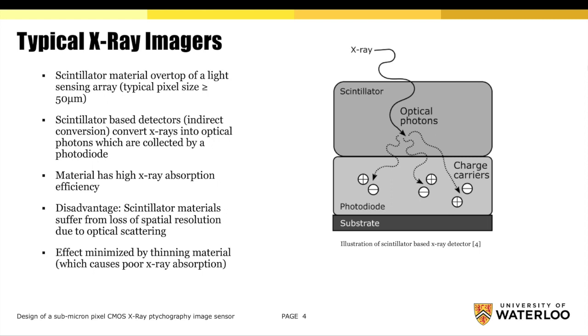Although this scintillator material has high x-ray absorption efficiency, the detectors suffer from loss of spatial resolution due to optical scattering. To minimize this effect the scintillator material can be thinned, however this leads to poor x-ray absorption, and because of this trade-off it's difficult to achieve smaller pixels using this technique.